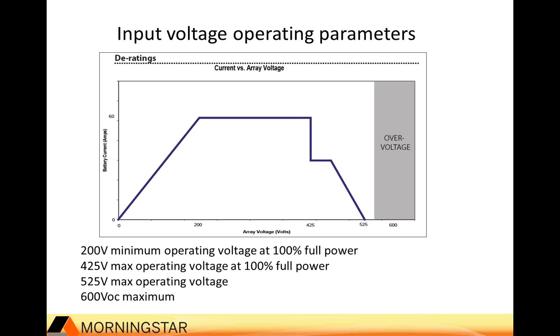And then when you get past a certain point on the open circuit voltage, around 550 or so, you're beginning to get into a high voltage condition where the product would not be able to operate because you're approaching the maximum open circuit voltage, which would be 600 volts. At that point, that's where the components are actually rated, so you would not be able to operate if the voltage was that high because the controller would be in a shutdown state. So you do have to size it so that even in extreme cold, you're not going to get into those high voltage areas near the engineering design threshold.